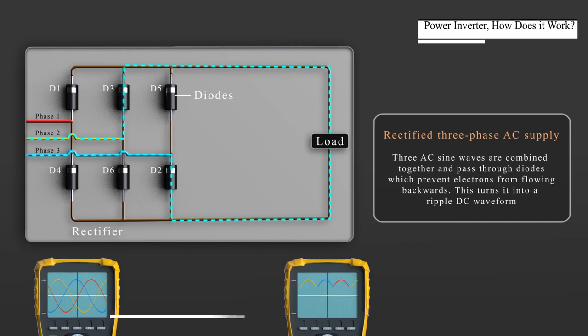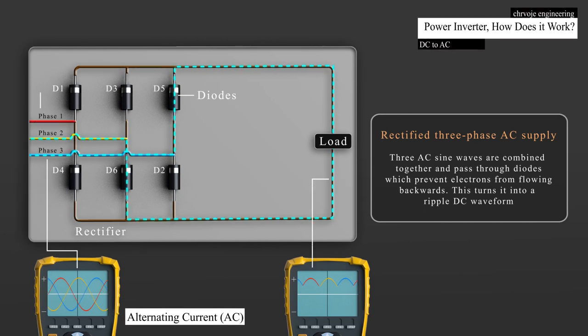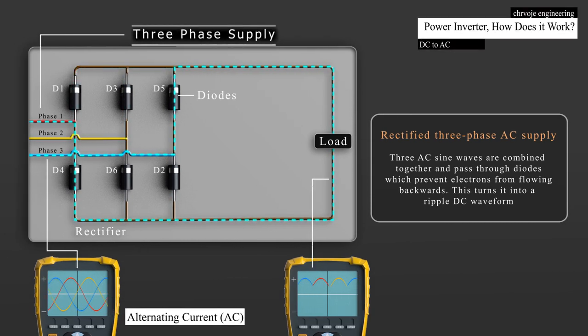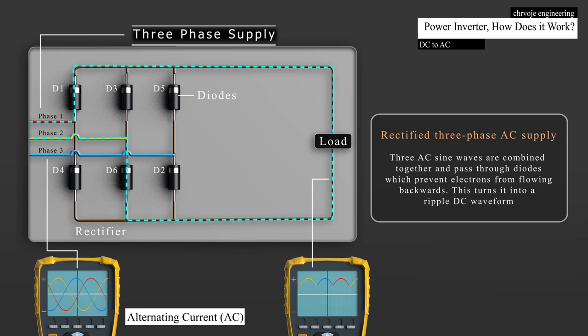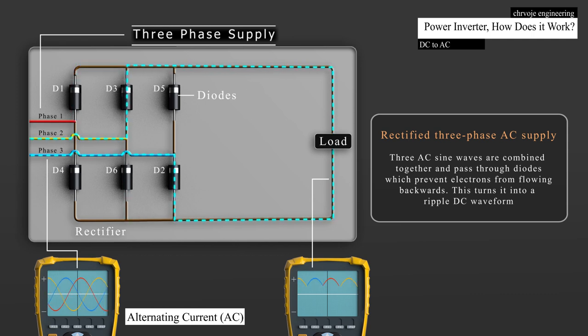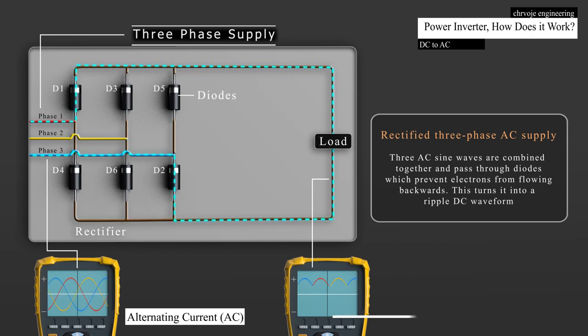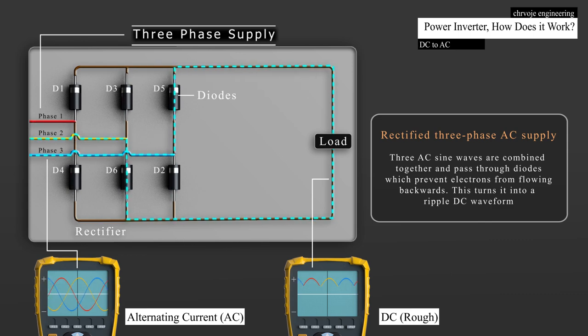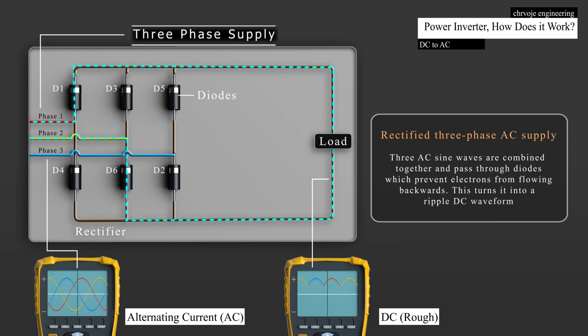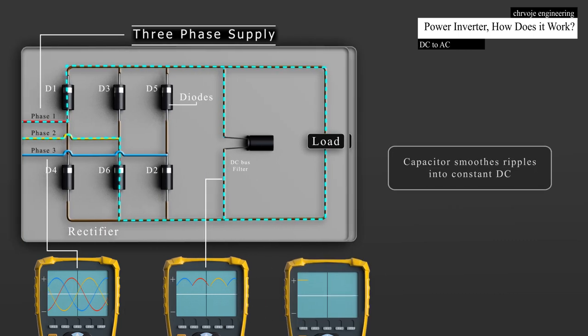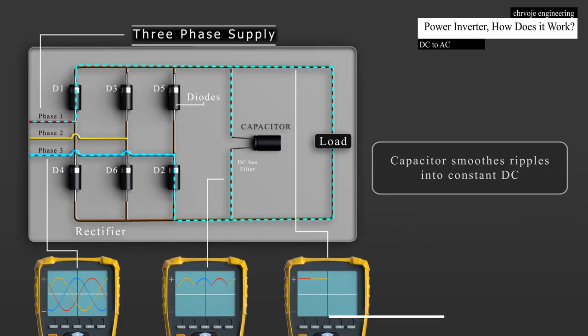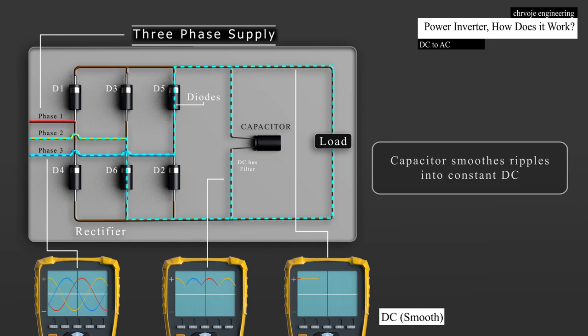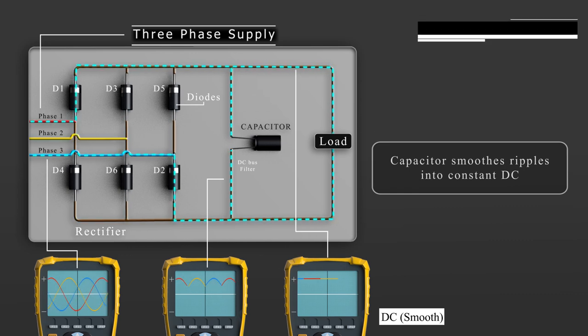The DC supply in this case will be a rectified three-phase AC supply. That means that three AC sine waves are combined together and pass through some diodes which prevent the electrons from flowing backwards. This turns it into a ripple DC waveform. We then use a capacitor to smooth the ripple out into a constant DC supply.